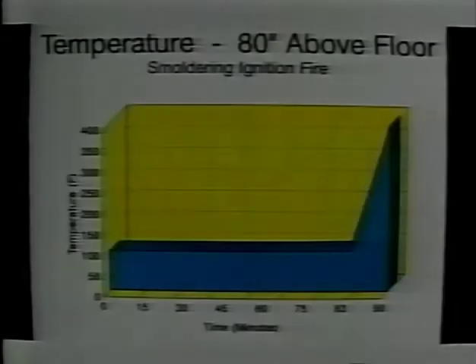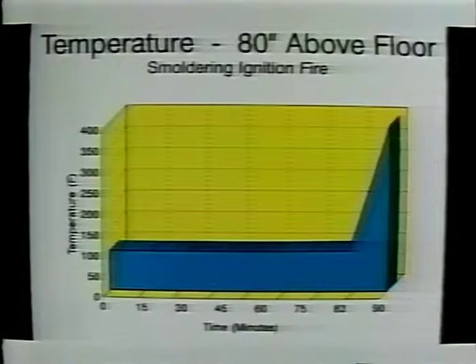Environmental sampling tubes penetrating the walls in the room of origin and hallway were connected to a pump located in the control room. The air samples collected through this system were analyzed to determine the oxygen and carbon monoxide levels. The previous fire indicated there was very little change in temperature during the smoldering process. At ignition, a rapid elevation in temperature was experienced. This is typical in a smoldering fire condition that ultimately becomes a flaming fire.